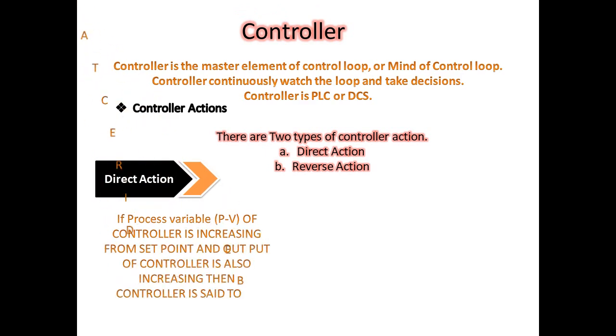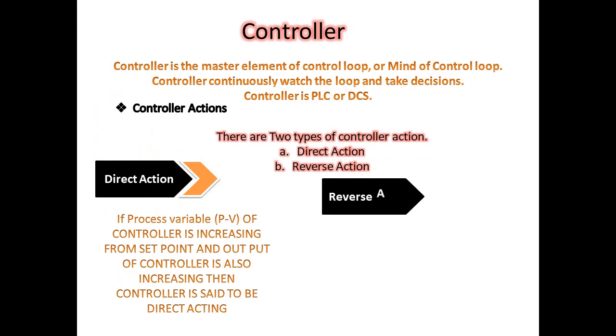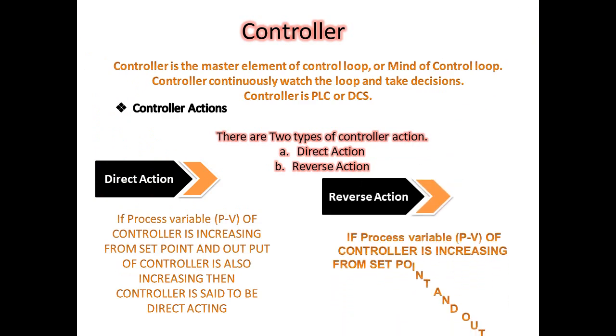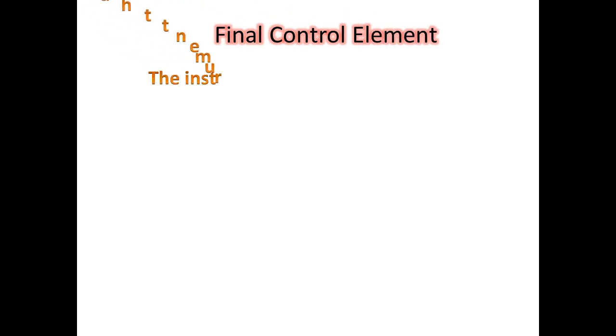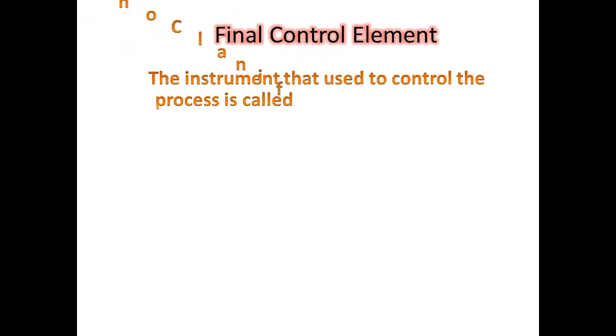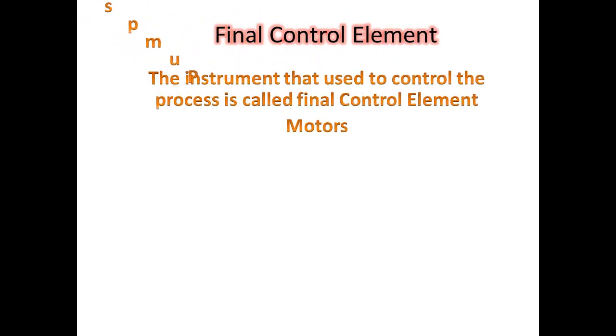In direct action, if the process variable of the controller increases from the setpoint and the output of the controller also increases, then the controller is said to be direct acting. In reverse action, the controller is said to be reverse acting when the output responds in the opposite direction to the process variable.